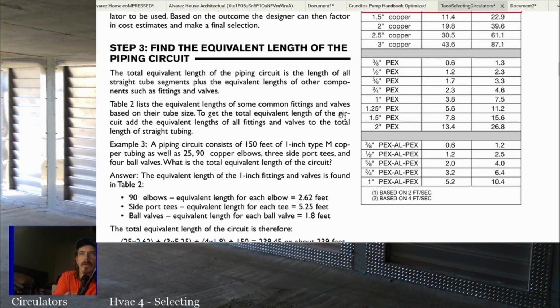So the next part is finding the equivalent length of the piping circuit. You do this in refrigeration, right? We especially do this in gas, but we'll talk about how long your run is on your refrigeration circuit when you're sizing refrigeration piping. And a lot of times people don't factor in the fittings, but the fittings technically matter, right? One elbow is like 5 feet of pipe or whatever. So we need to find the equivalent length for the piping circuit when we're talking about a boiler system too. The only thing is, in a boiler system, the lengths for the fittings matter a pretty reasonable amount, especially when you're talking hard copper 90s or steel 90s or something like that.